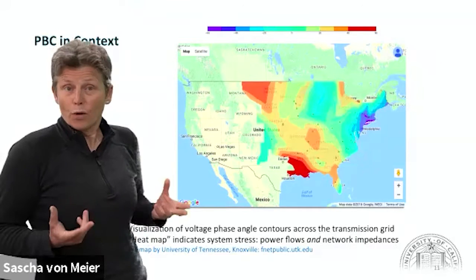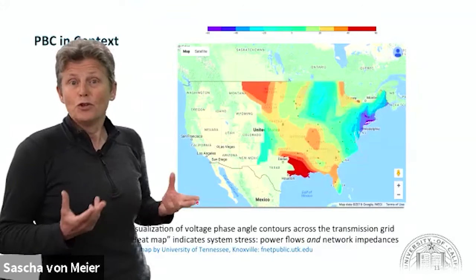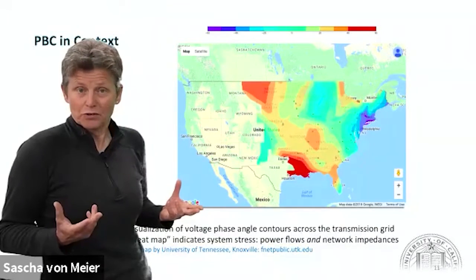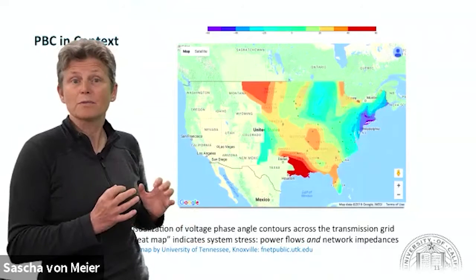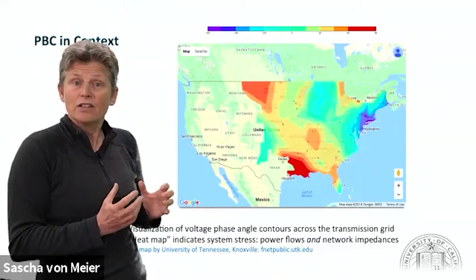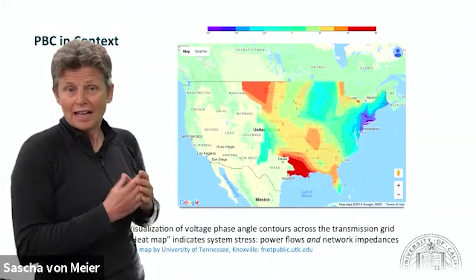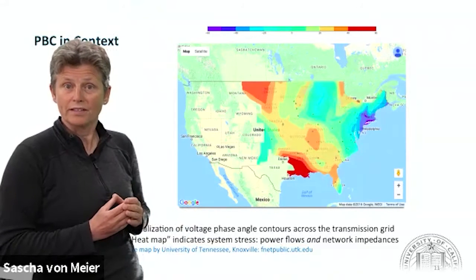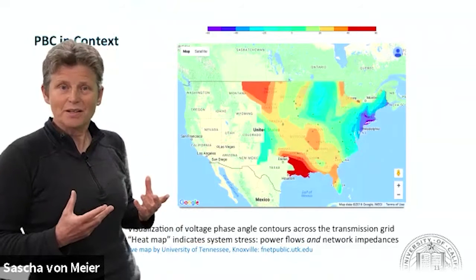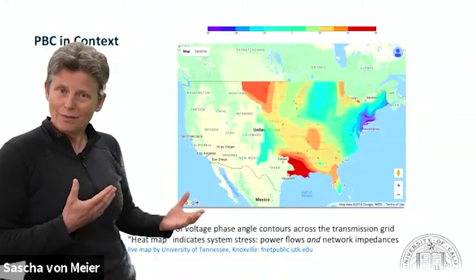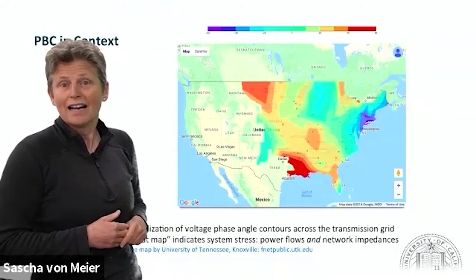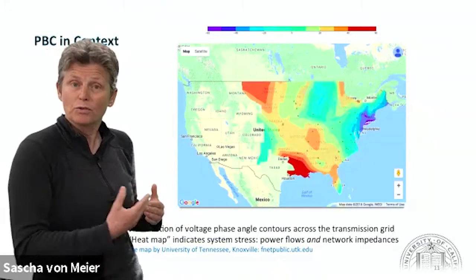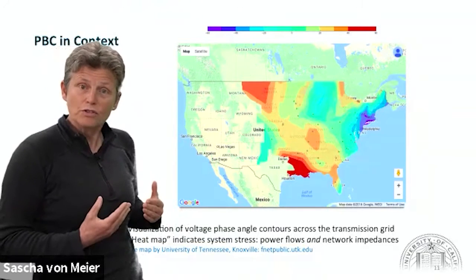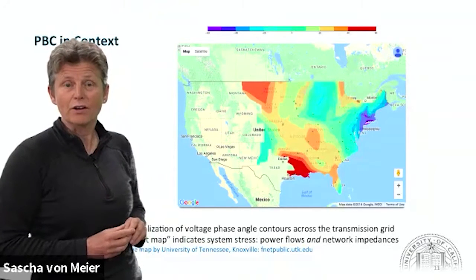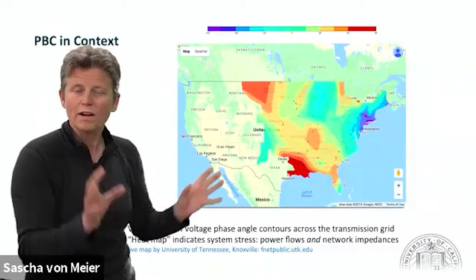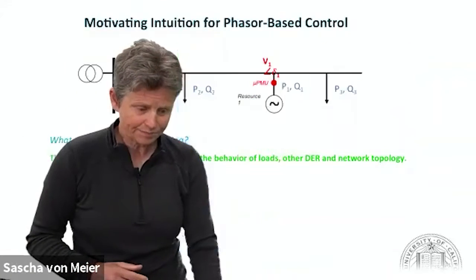Now, interestingly, for voltage control, we're already doing automatic voltage regulation, where generators are injecting as much reactive power as it takes to maintain a certain voltage magnitude at their bus or interconnection point. In transmission systems, because of that dominance of X over R, it's sufficient to just use reactive power to manage voltage magnitude. In distribution systems, all these variables get mixed together. So the concept here is, what if we control all of it together?